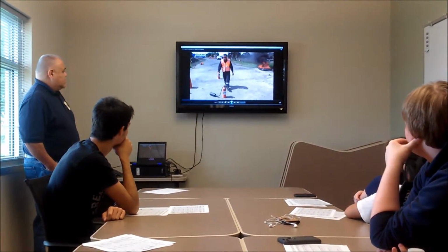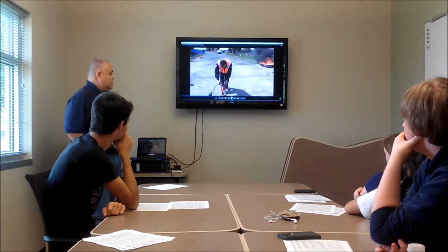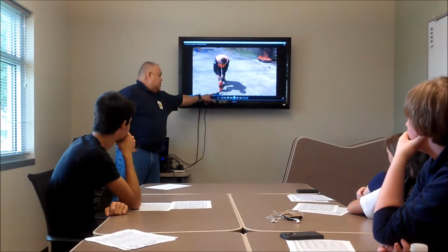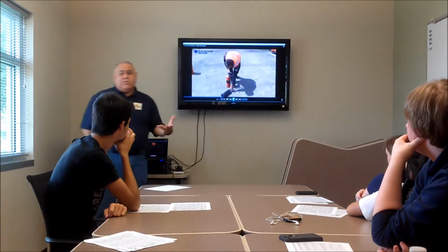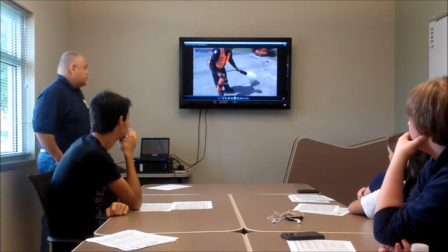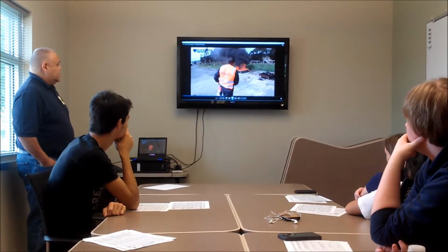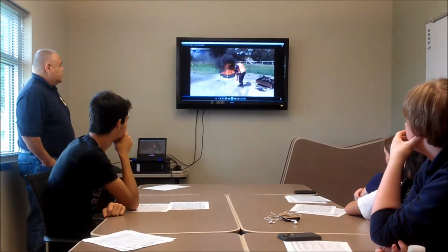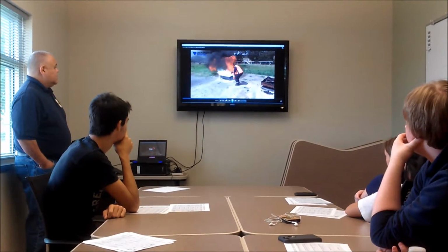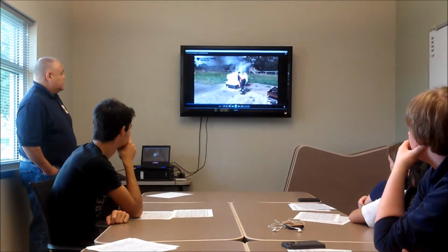This time John's going to use a CO2 extinguisher. So the same sort of technique, no gauge on this one though. You can see his cone is bigger. You never want to grab the cone. You want to grab it by the handle, because otherwise it'll burn you. He's tested it, squeezed. Now, the only thing we're a little bit concerned about today is the wind, so you may not have enough to go in this extinguisher, but you're going to give it a go anyway. See how it's slipping back behind there?